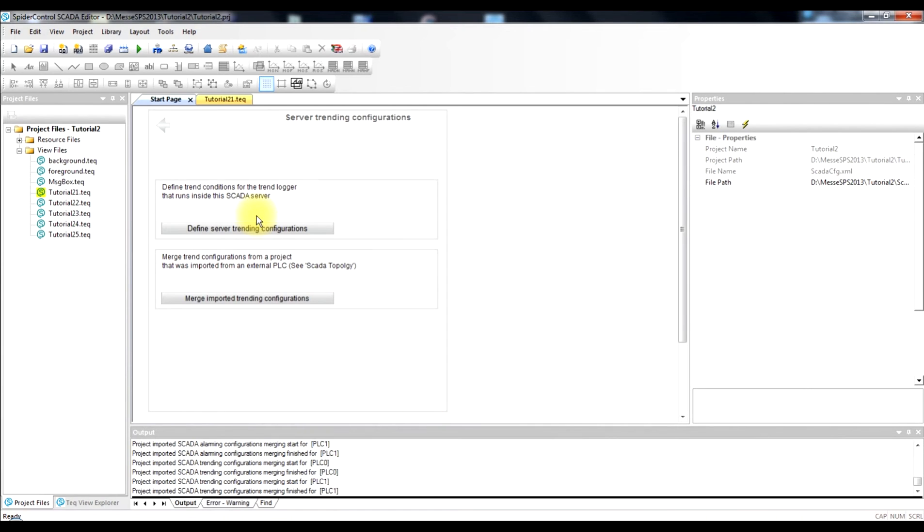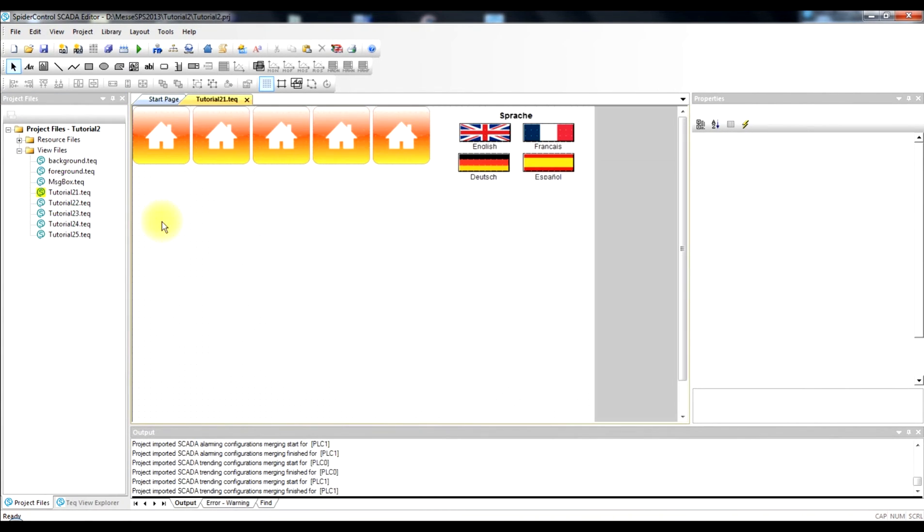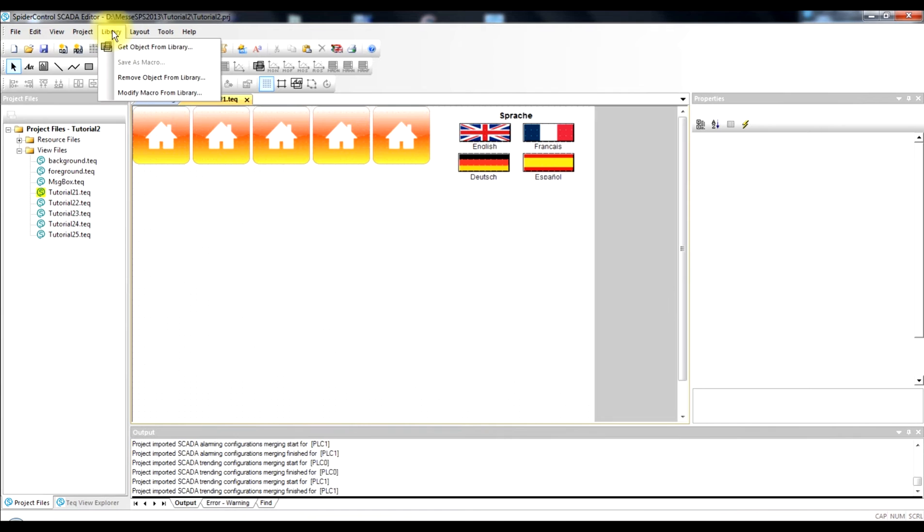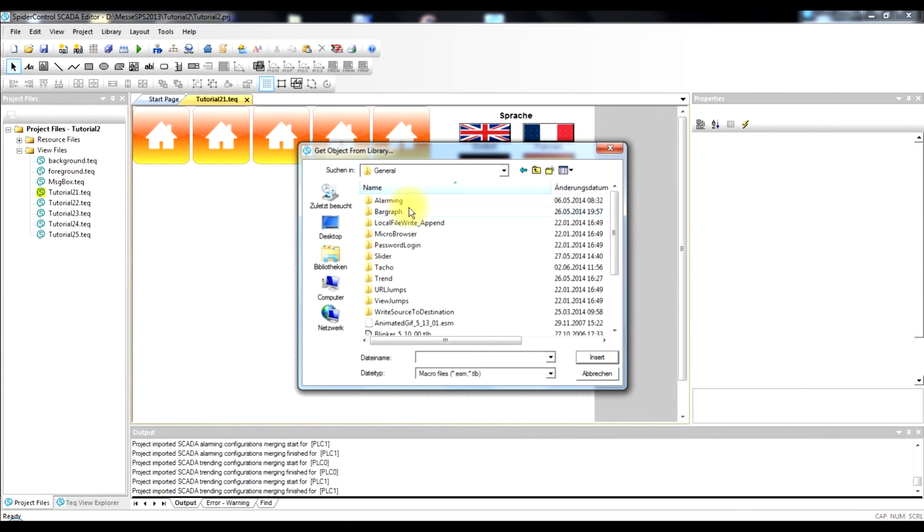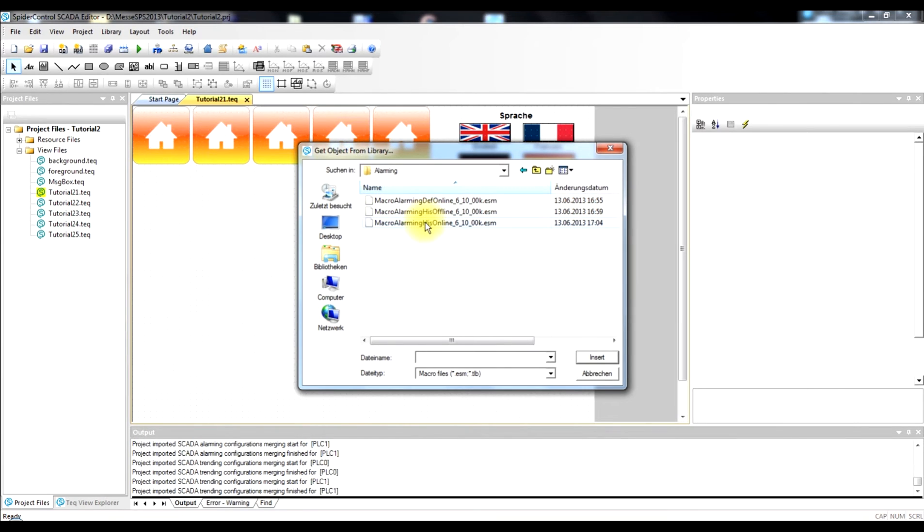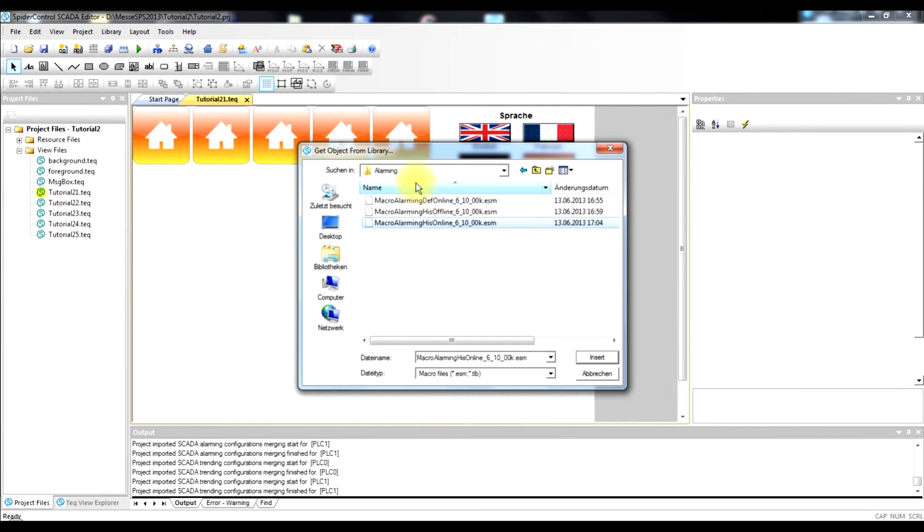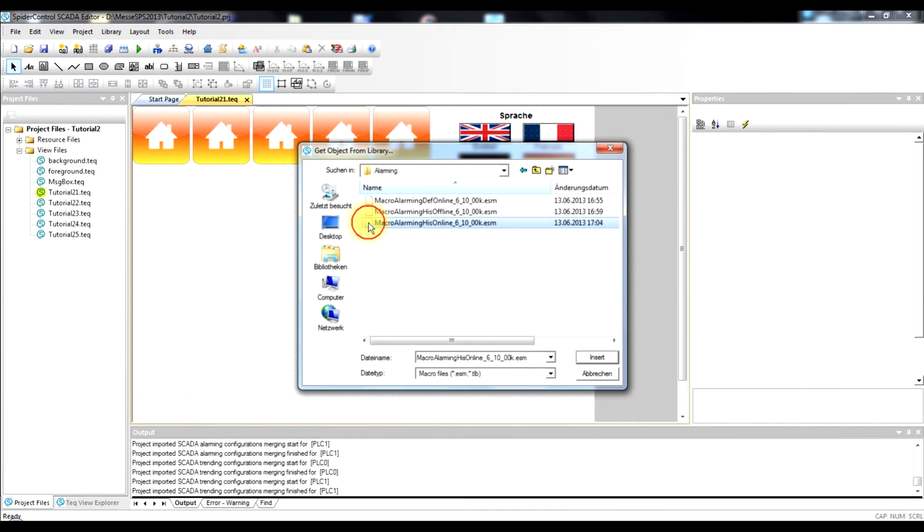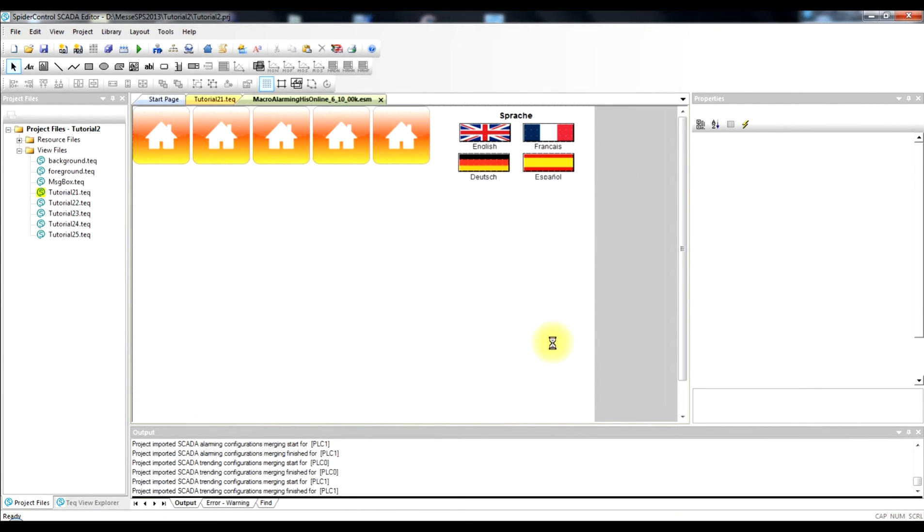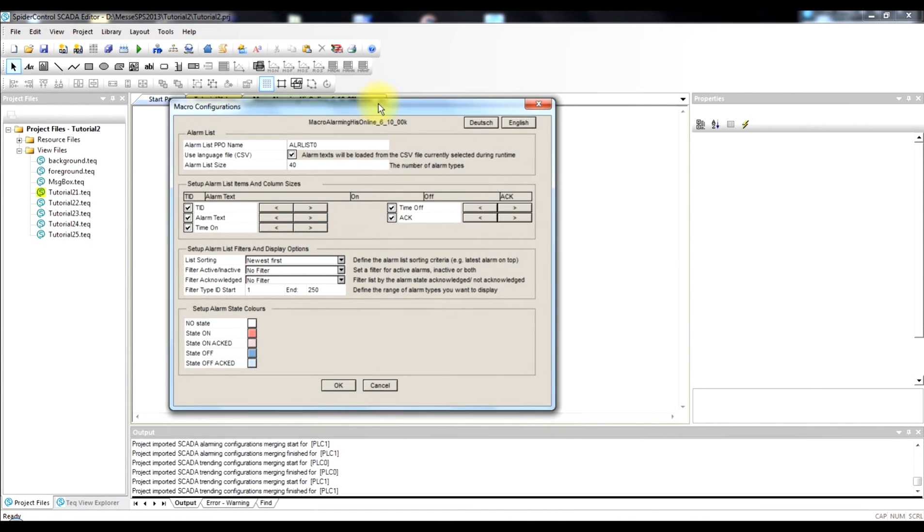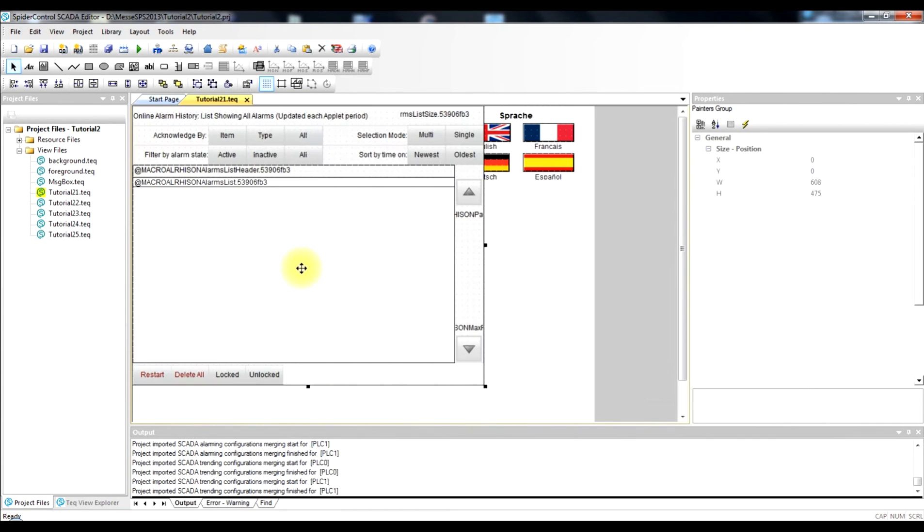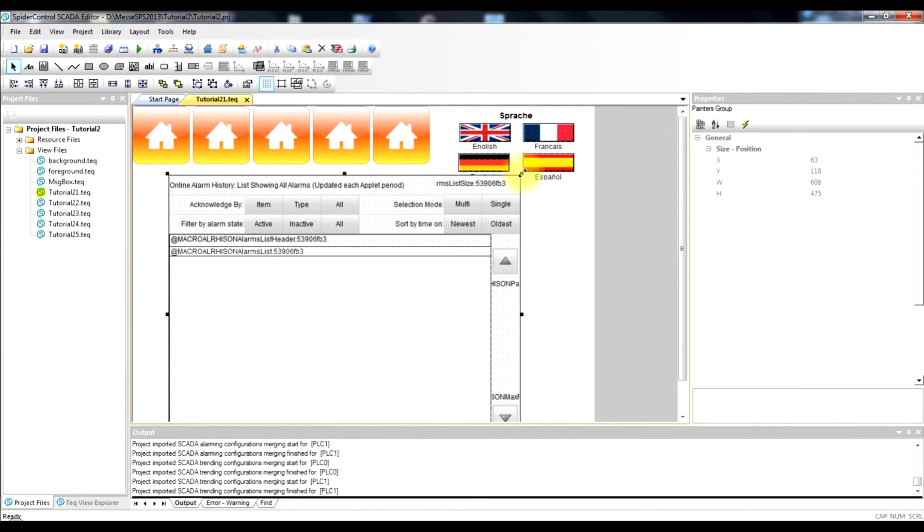So our SCADA server is now set and we can move over to create the HMI. So we will add graphical objects to display our alarm lists and our historical trends. For this we take a macro from the macro library. We go to the alarming directory and choose the macro alarming history online. There are several types but history online is the one that is mostly used, which gives us a live overview of all incoming alarms and their states. So this will add the macro. In this macro dialog you can configure a lot of details. But basically you just have to click OK and you are set.